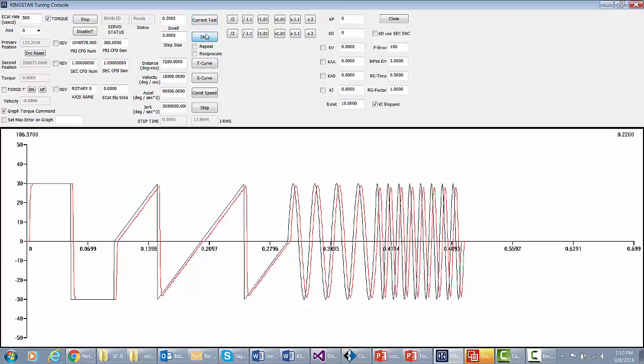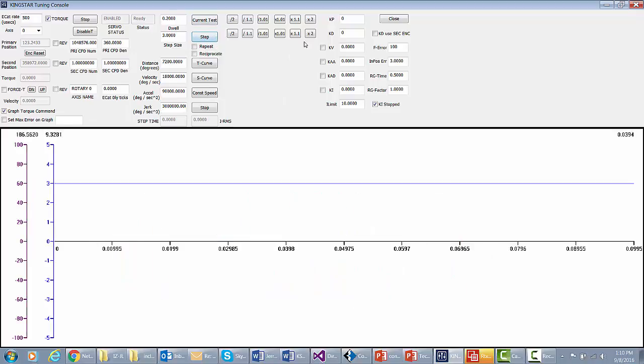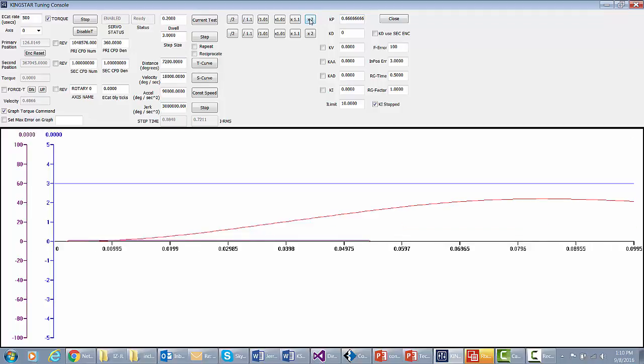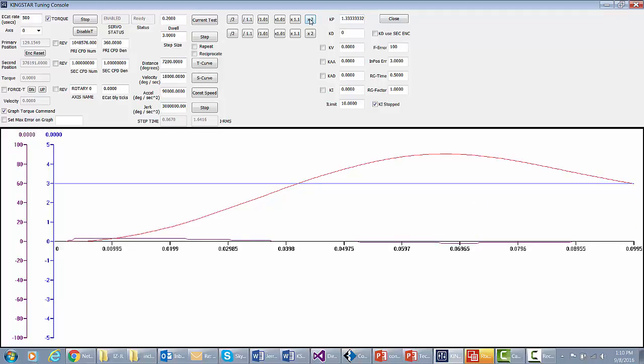So we're going to go in here and do a step. All of our parameters are set for zero, so I'm going to double Kp, which puts in 1%, and I'm just going to keep doubling Kp until its response is a little too big.